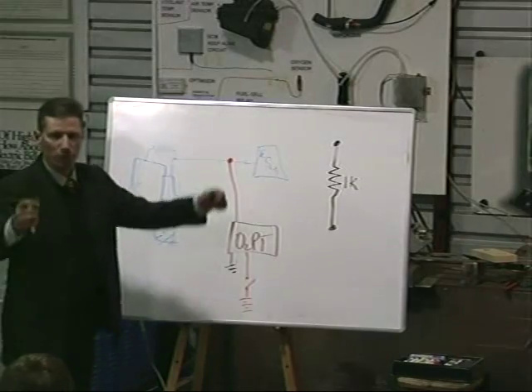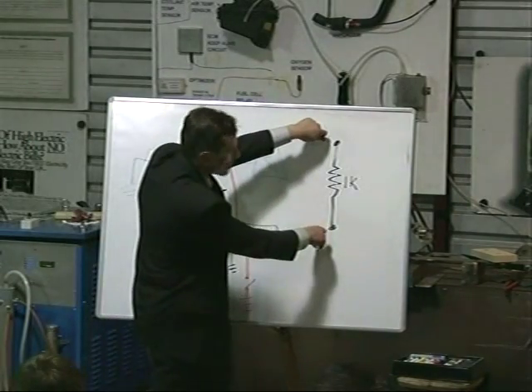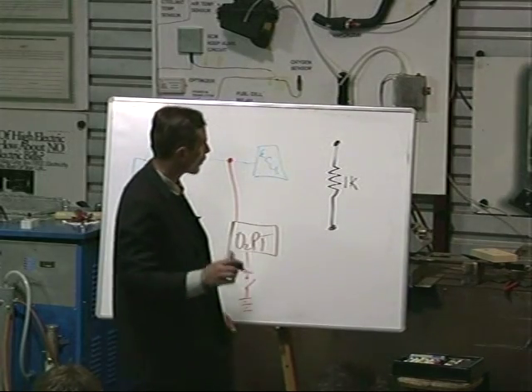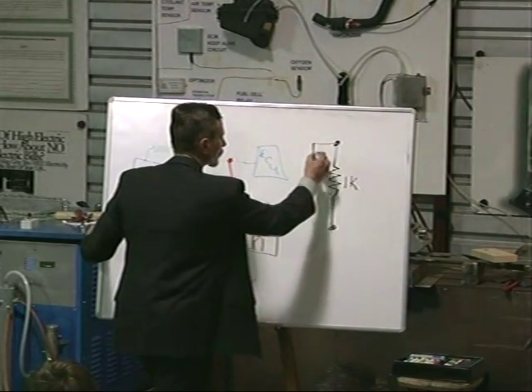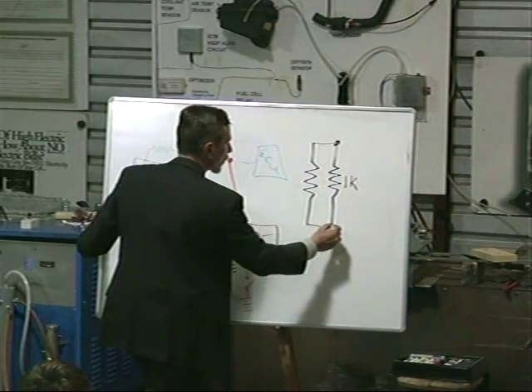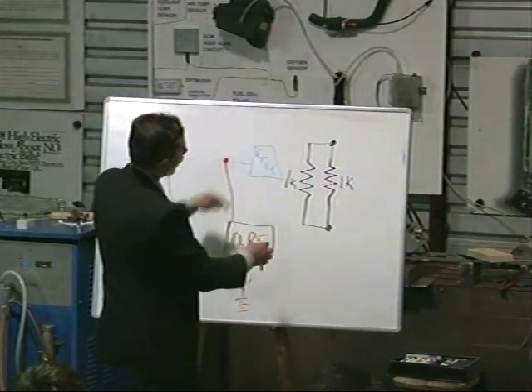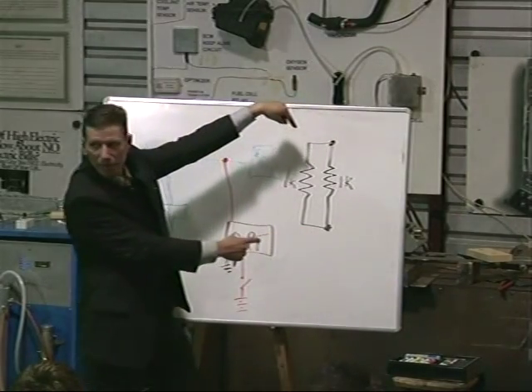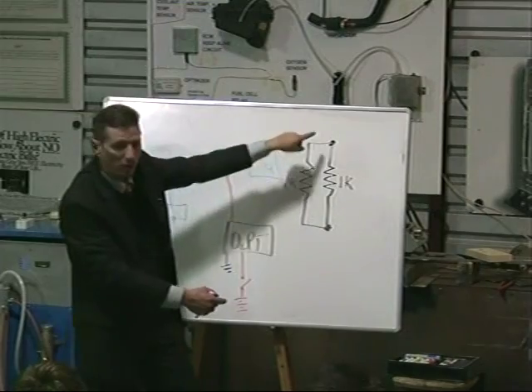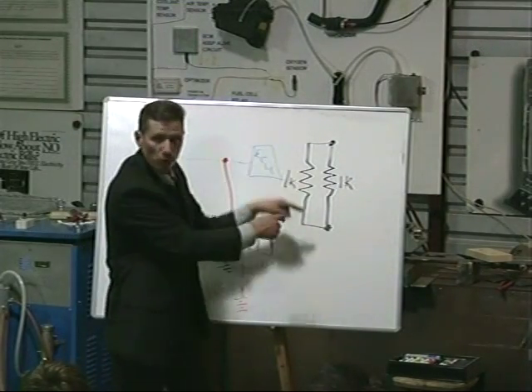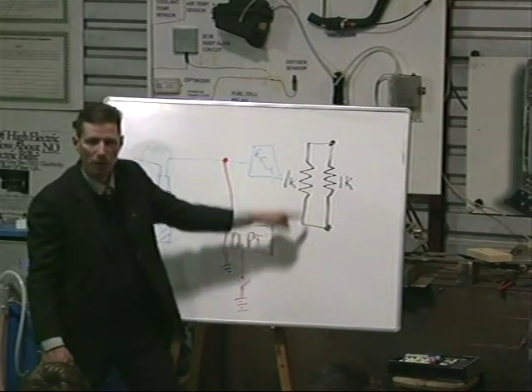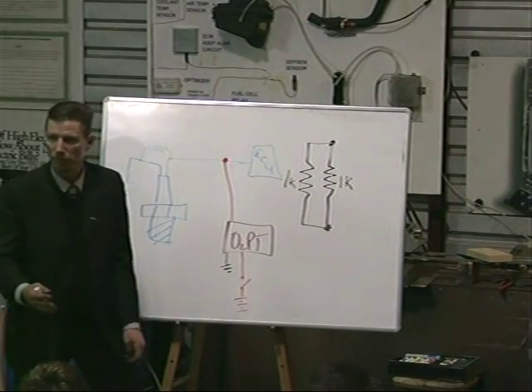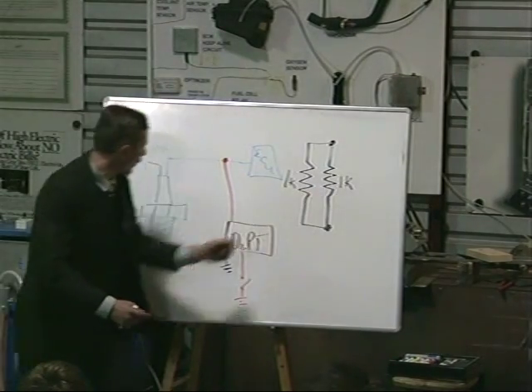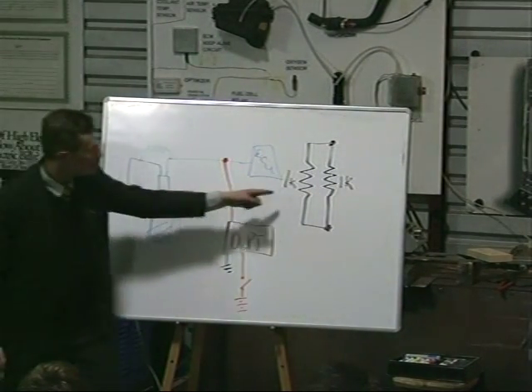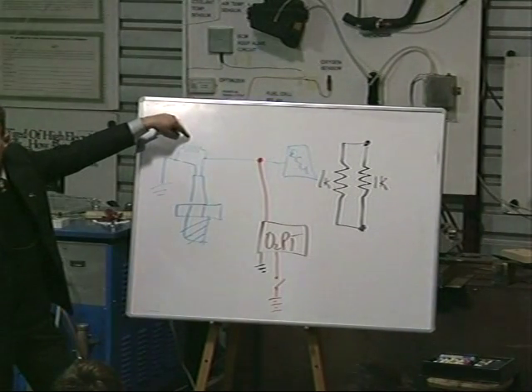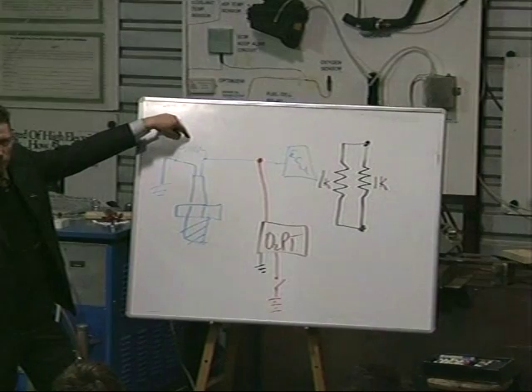One K ohm resistor. If we take our ohm meter, put it across there, it's 1,000 ohms, 1 K ohms, right? Now, if I do this, and I put my ohm meter across here, I'm going to read a half K ohm, 500 ohms. When you go in parallel, you're going to split the resistance two ways. So 1,000 ohms and 1,000 ohms in parallel will give me 500 ohms. One side is going to be your actual sensor. The other side is going to be the optimizer circuit.